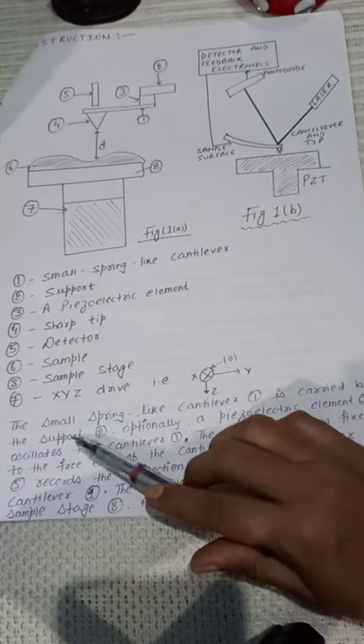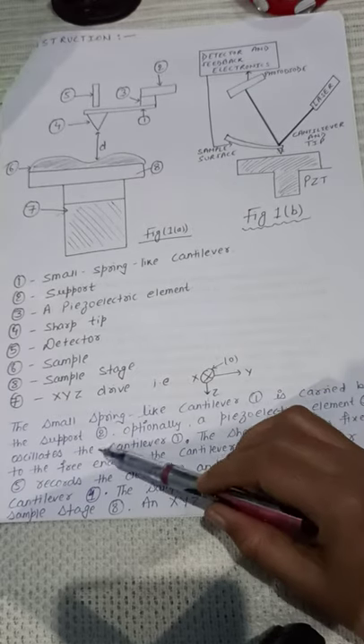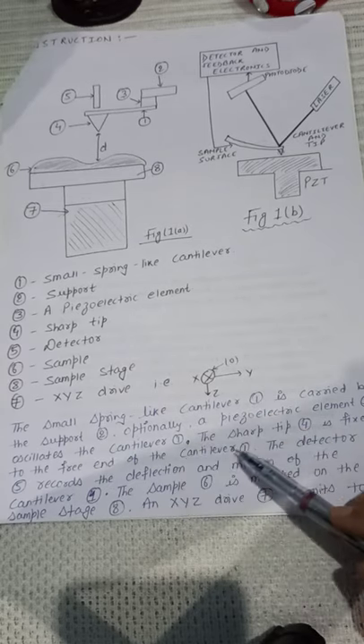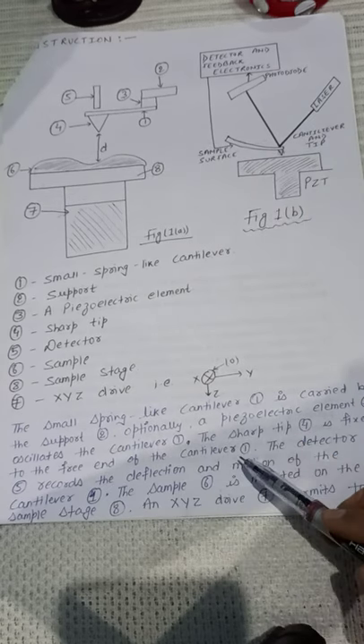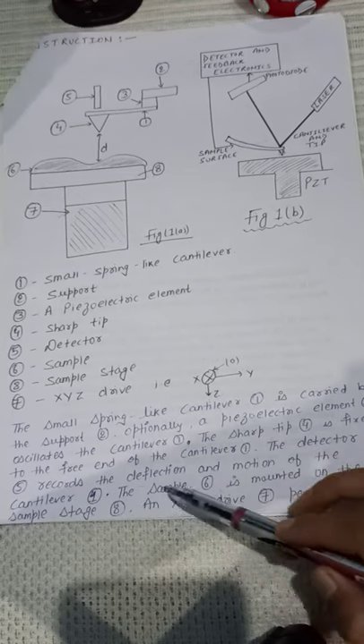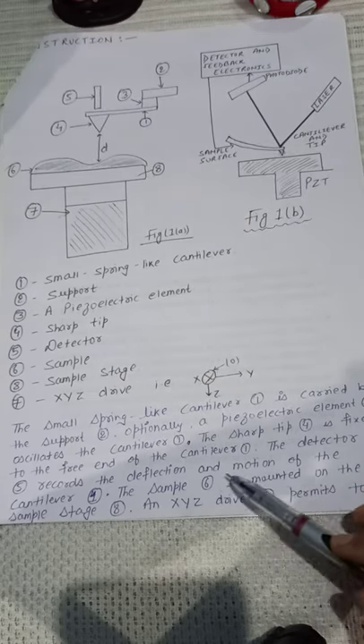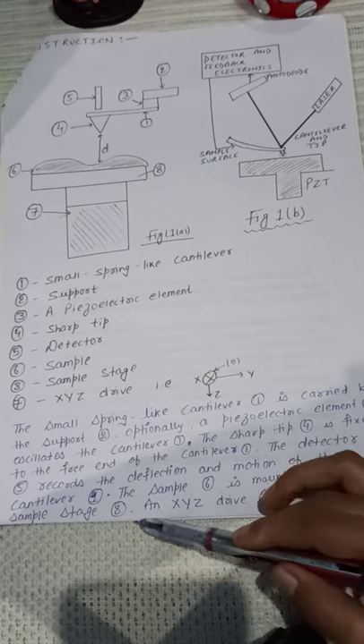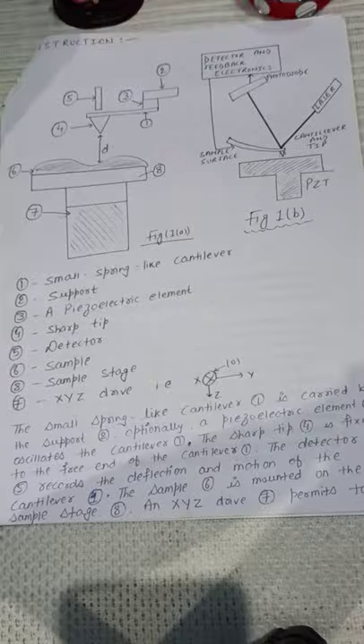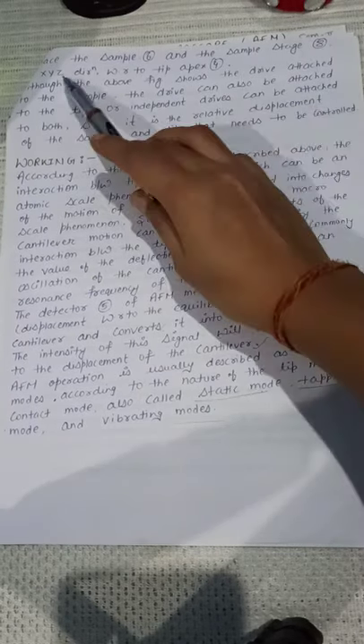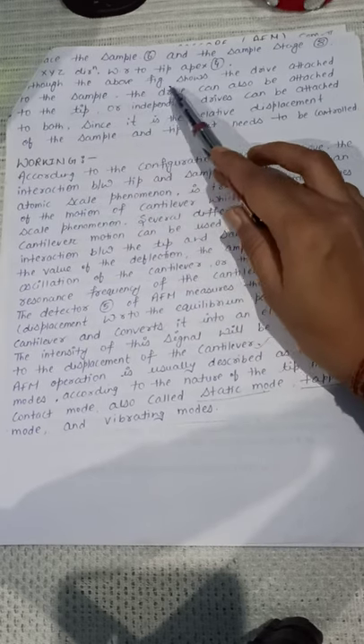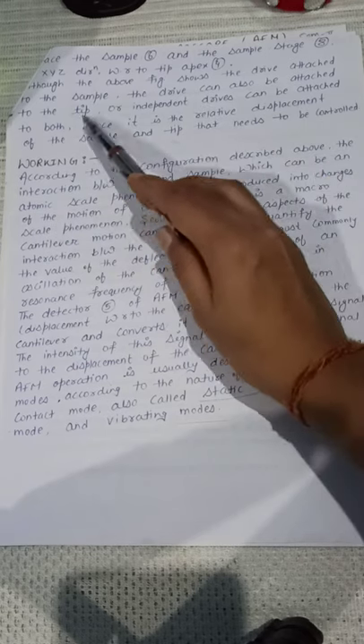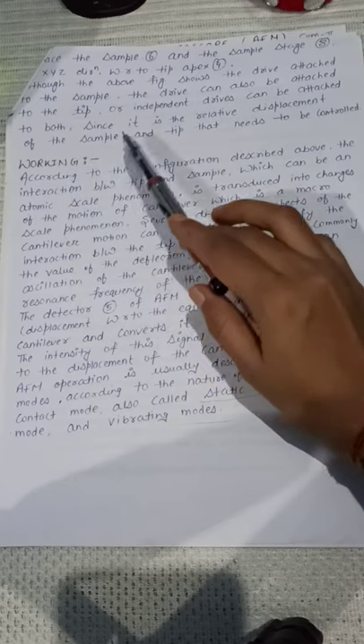The small spring-like cantilever (1) is carried by the support (2). Optionally, a piezoelectric element (3) oscillates the cantilever (1). The sharp tip (4) is fixed to the free end of the cantilever (1). The detector (5) records the deflection and motion of the cantilever (1). The sample (6) is mounted on the sample stage (8), and XYZ drive (7) permits to place the sample (6) in XYZ direction with respect to tip apex (4). The above figure shows the drive attached to the sample. The drive can also be attached to the tip or independent drives can be attached to both, since it is the relative displacement of the sample and tip that needs to be controlled.